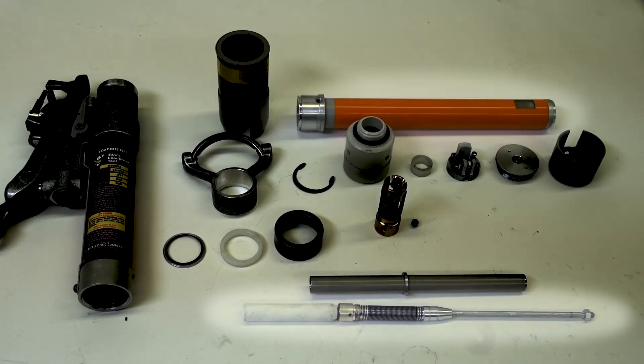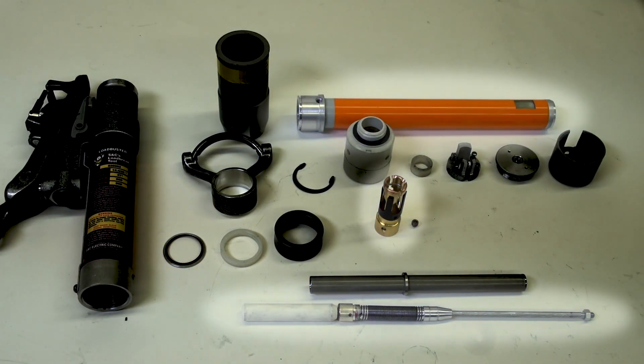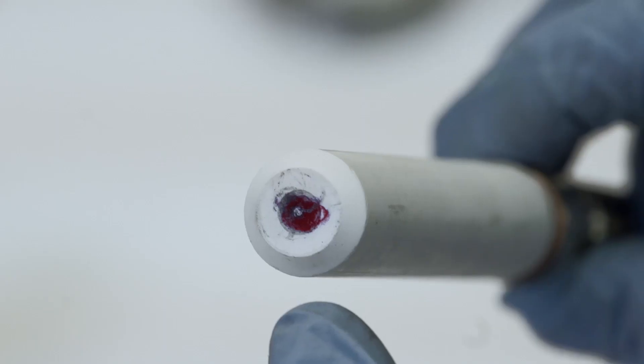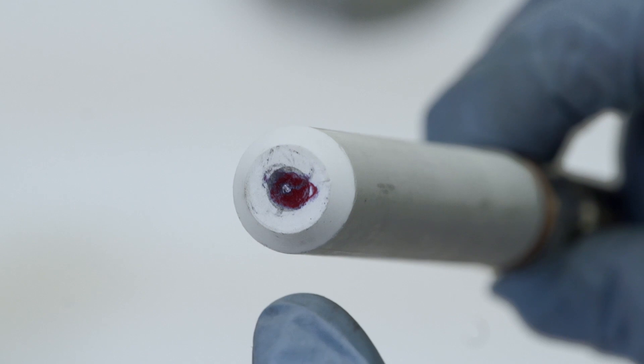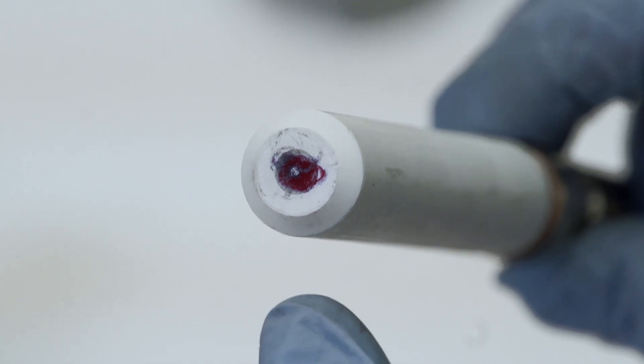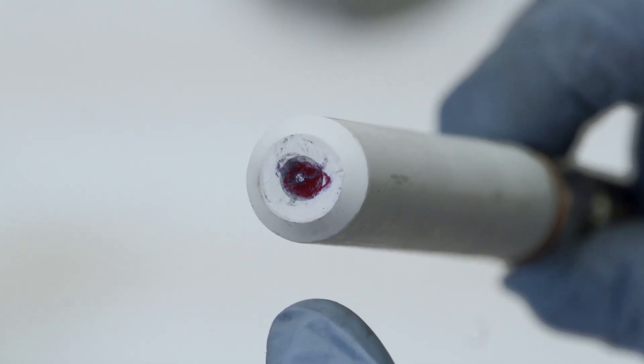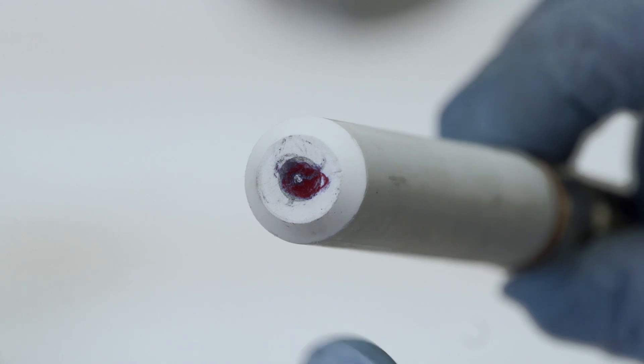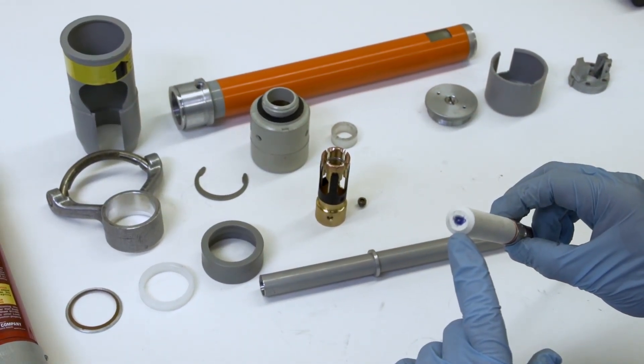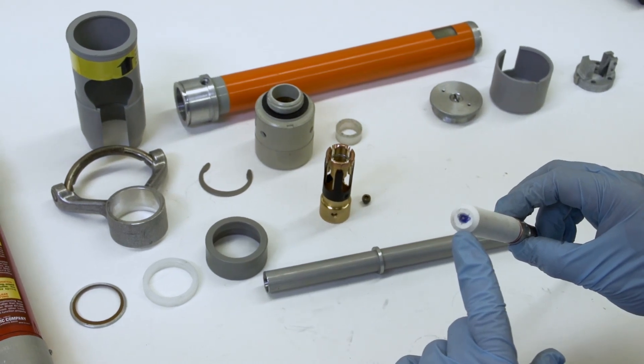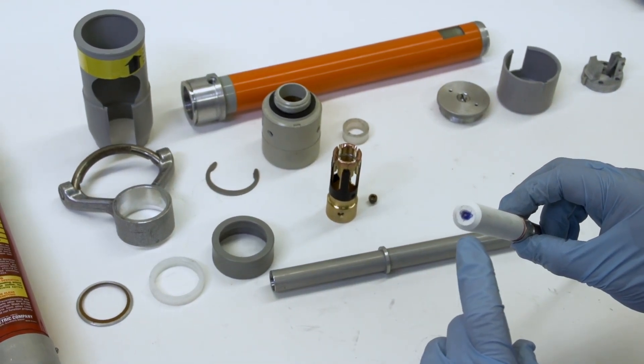Replace the inner tube assembly, stationary contact assembly, guide bearing, and silencer at the same time. Note that moving contact assemblies manufactured prior to August 2002 that have a red dot on the end of the trailer can be operated 500 to 1,000 times before inspection and maintenance are required. Tools with moving contact assemblies with a blue dot on the trailer can be operated 1,500 to 2,000 times before inspection and maintenance are required.